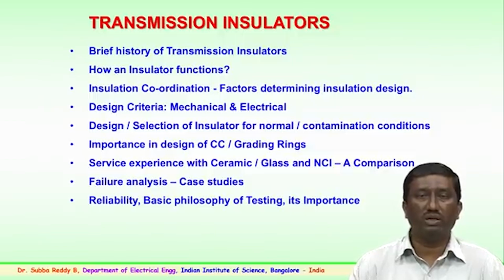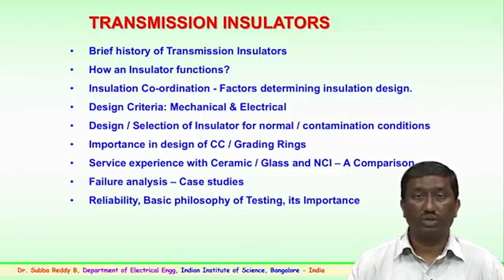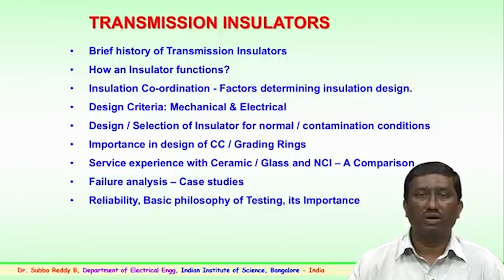How important is the design of the corona control rings, or grading rings? We will have a look into that. This is a very important aspect for the insulator string, where it has multiple functions. So, we will discuss the importance of the design of the corona control rings. And the service experience of ceramic and glass, which have been used for more than 100 years in the transmission system. We will look at the experiences with ceramic and glass, and mainly at the non-ceramic insulators, or polymer or silicone rubber insulators, which are very important and of recent origin, and are being employed for EHV and UHV transmission.